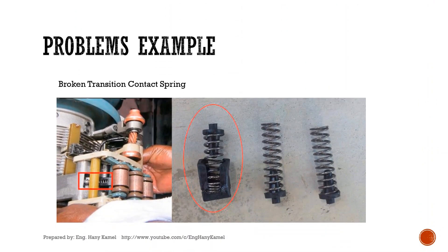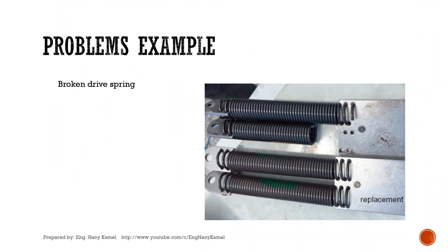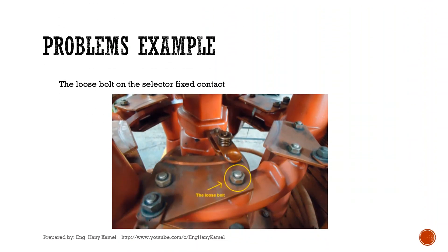Here are some examples showing how effective the test is. In the first example, the test curves showed a deviation; the tap changer was opened and a broken transition contact spring was found. In another example, a curve deviation was found; the tap changer was opened and a broken drive spring was detected. In a third example, there was a curve deviation; the tap changer was opened and a loose bolt on the selector fixed contact was found.